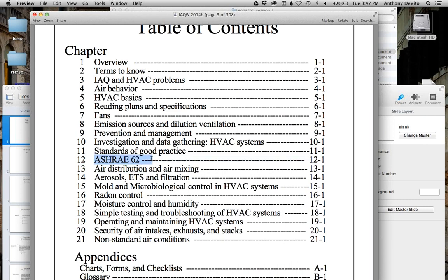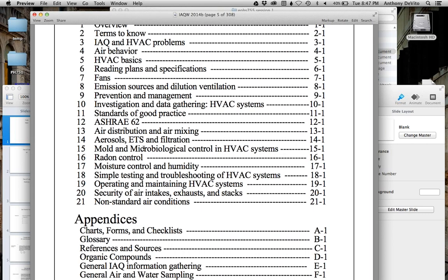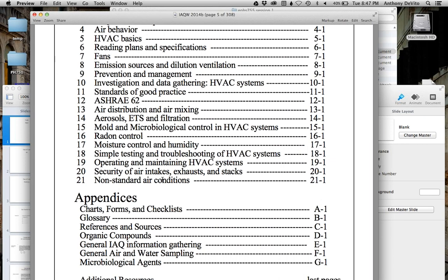Most indoor air quality is associated with dilution ventilation because sources are so distributed inside a building — we're not going to put a hood on everybody's pen. The book discusses things specific to indoor air quality including standards. There aren't very many solid standards applicable to indoor air quality, but a few are applied to various situations. Other issues that come up include mold and radon. Radon is the second most common cause of lung cancer in the United States — number one is smoking, number two is radon.